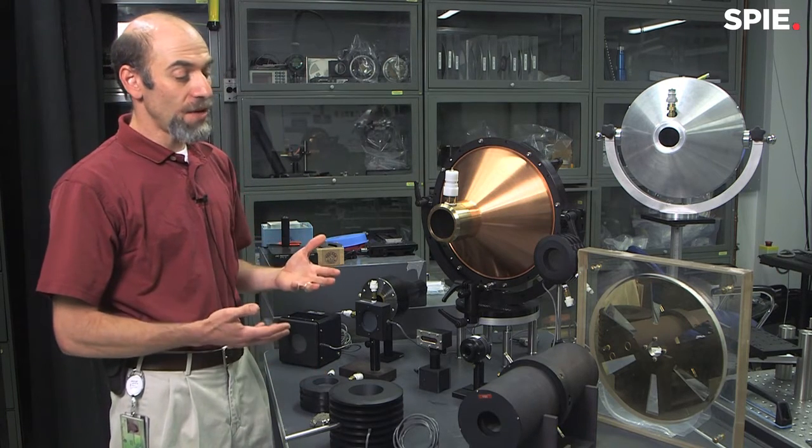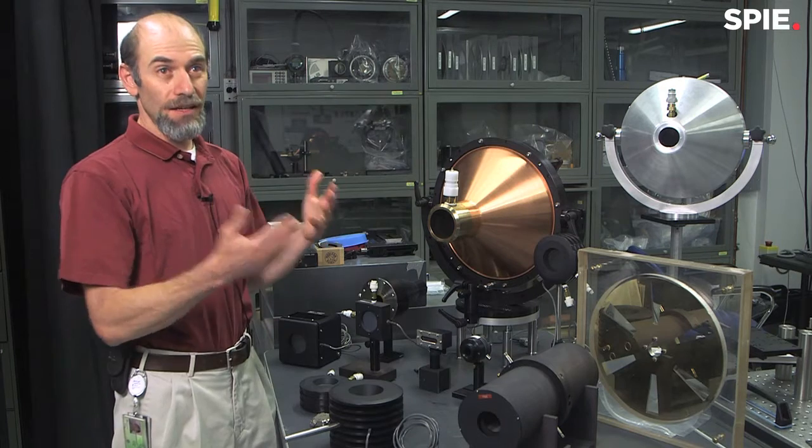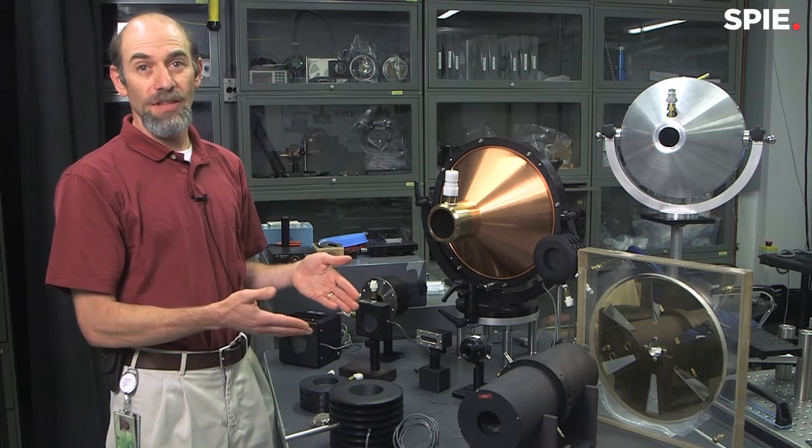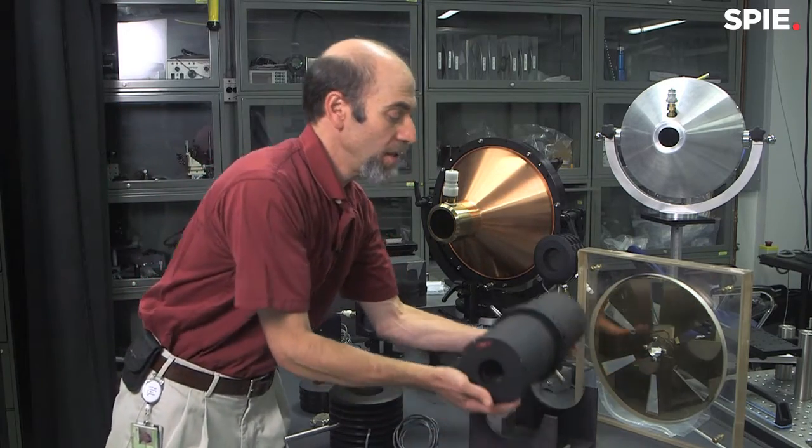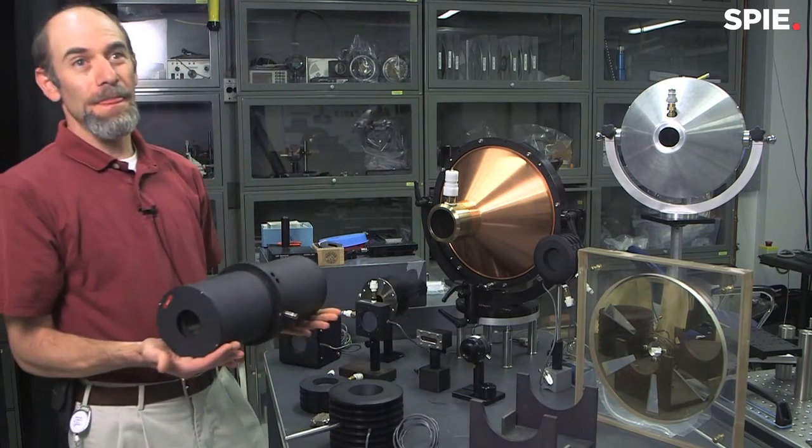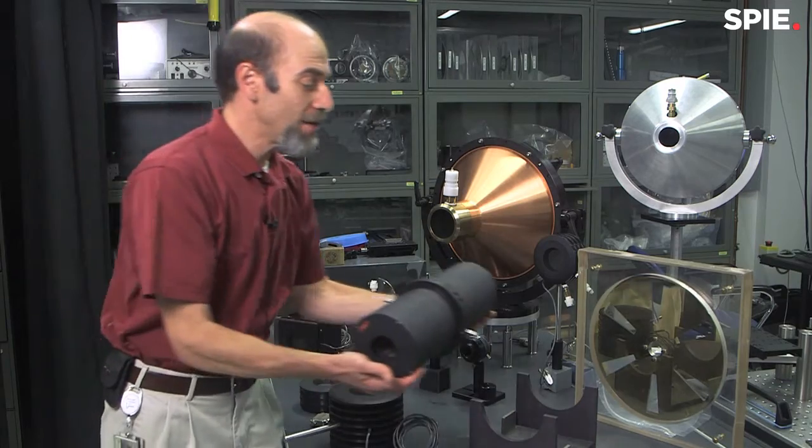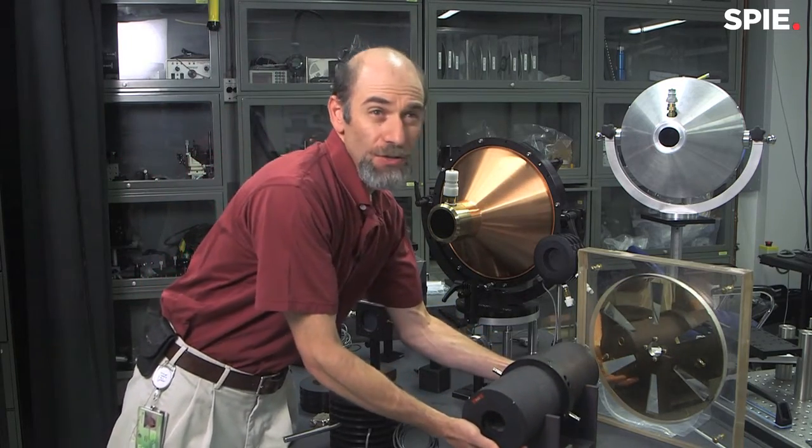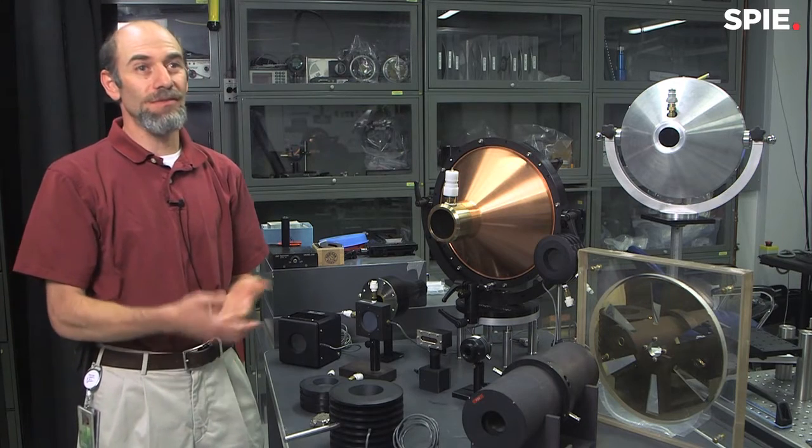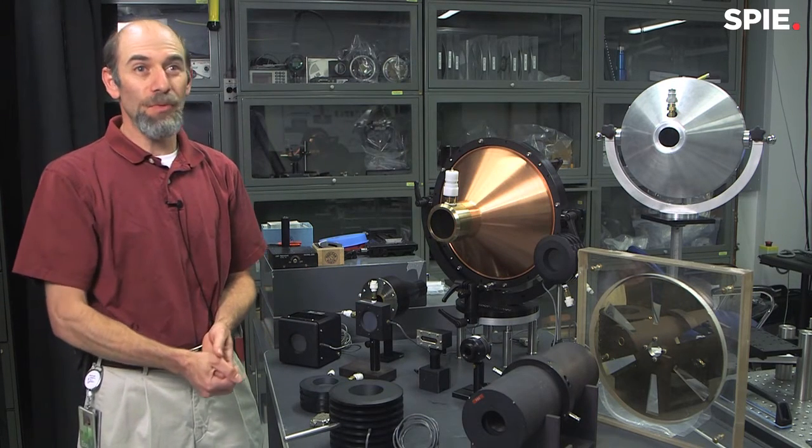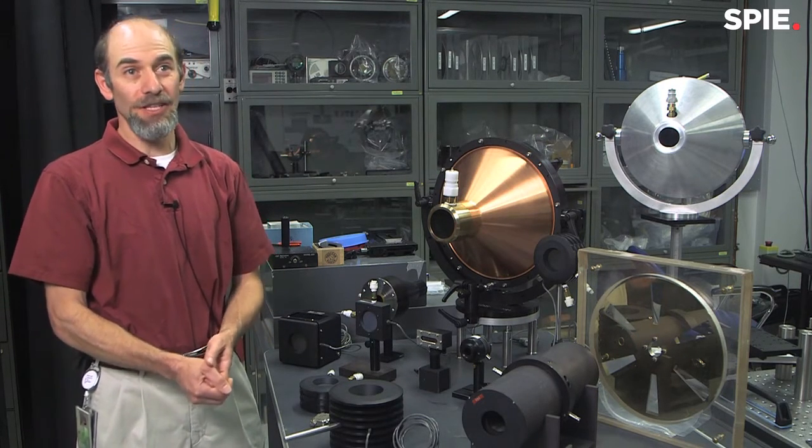The measurements that we do here are all tied to electrical standards that are established here at NIST. Our primary measurement is by calorimetry. Here's an example of our calorimeter. It allows us to accurately measure laser power to about 1%. Most of the applications in this realm, 1% is a pretty good accuracy for these measurements.